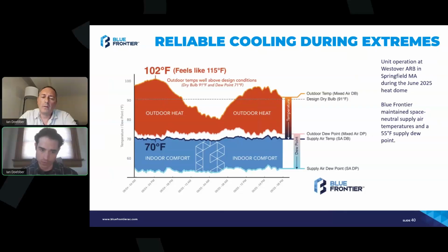We got to the low 70s dew point, which is very high and uncharacteristic for that part of the country. In the red here, we see that the outdoor temperature, as it made its way through our heat exchanger, was brought down to space neutral. This is a DOAS application. We were serving a bowling center, and we brought the air down to 70 degrees Fahrenheit. Then we took the outdoor extreme high dew points and brought those down to around a 55 dew point.